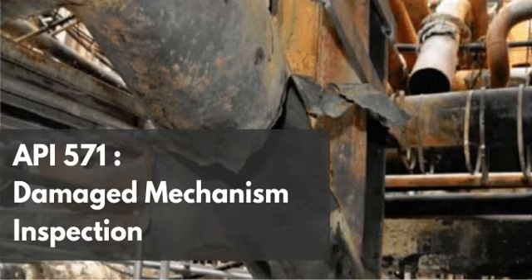It reverses the capillary action and aggressively pulls the trapped dye back out of the microscopic cracks, staining the white powder. Wow. So the invisible crack suddenly appears as a stark, bright line indicating exactly where the rolled joint is failing. That's right. It makes the invisible visible. That works brilliantly for the ends of the tube that you can physically reach at the tube sheet.